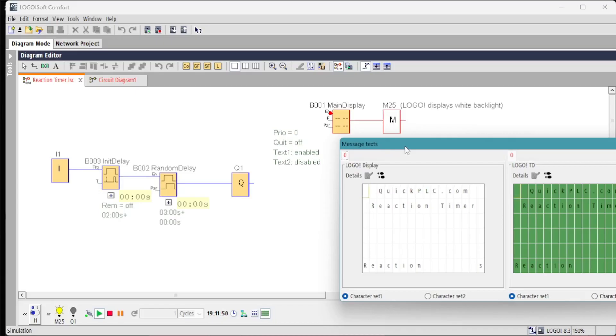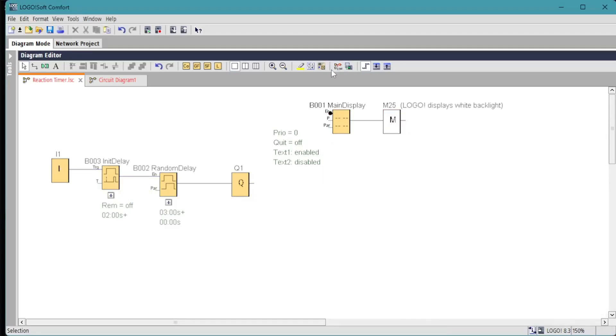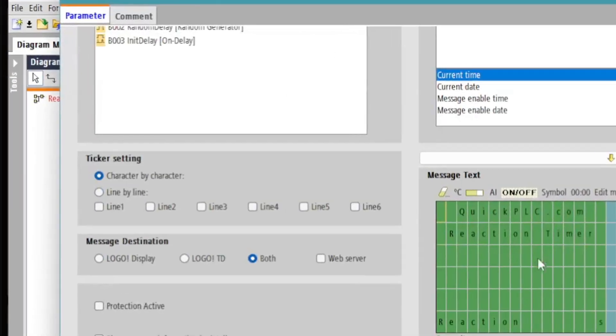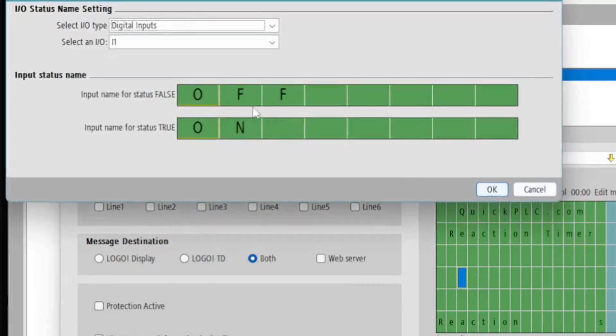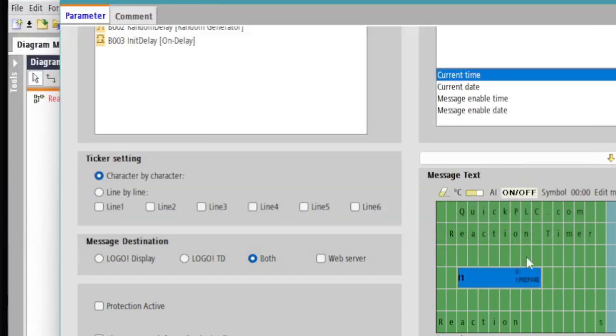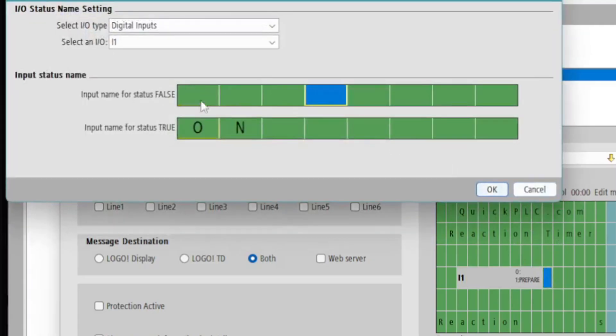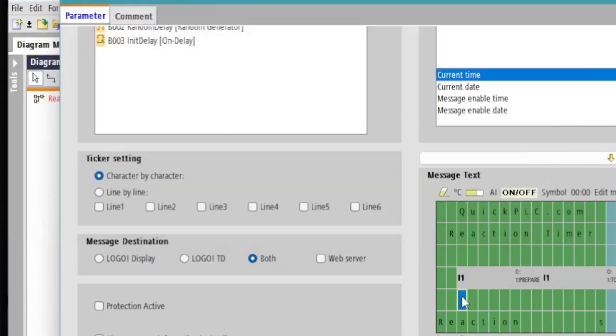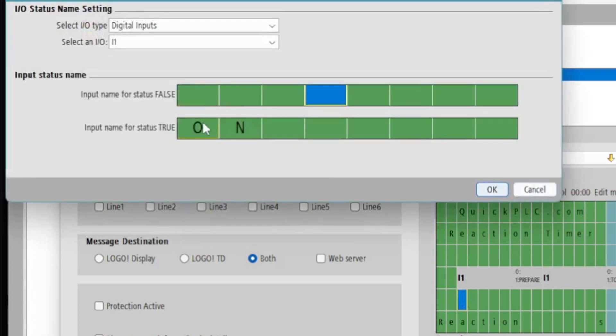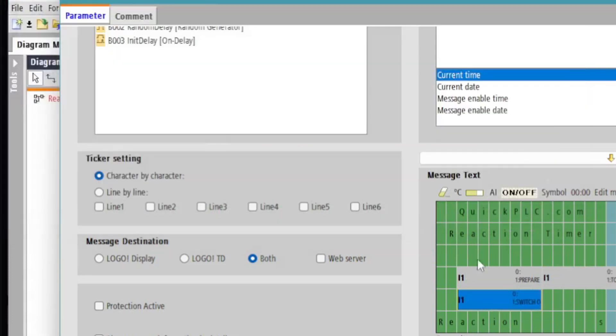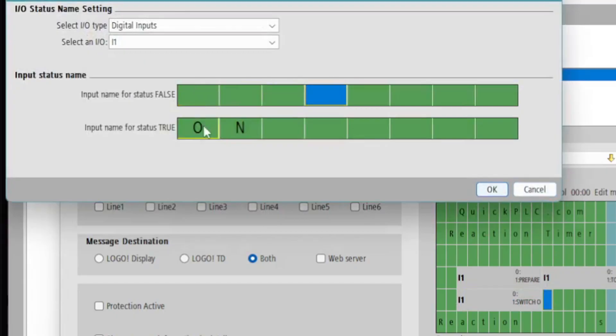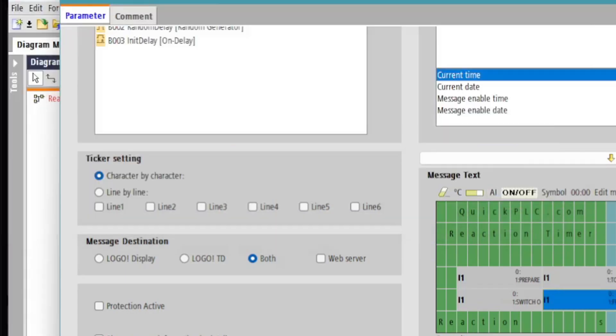We're going to use a little trick in the text message. We want to display a message to instruct the user when input one is switched on to get ready for the timer. There's an on/off function which will display one of two texts based on the digital signal. In this case we want nothing when input one is off and we want the prepare to switch off text message. So the strings are limited to eight characters, but we can use them multiple times, all triggered by input one.